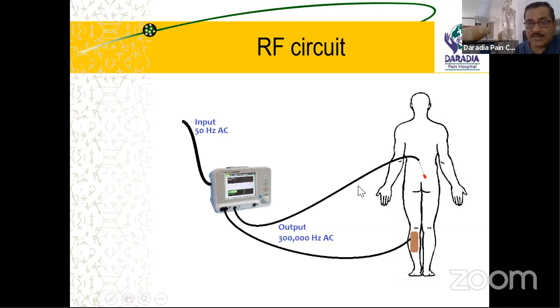Now, the principle as we discussed is that the probe itself is not heated, and the lesion size in conventional radiofrequency is around 2 to 4 millimeter. Beyond that, the electricity is dispersed so much that it is too weak to produce any thermal lesion. So the size of the lesion is 2 to 4 millimeter, not more than that. It has an advantage and a disadvantage. What is the advantage? It is not going to damage the surrounding tissues. But what is the disadvantage? If your needle is a little bit away, more than 4 millimeter away from the nerve, there will be no lesion. That means failure will be certain.